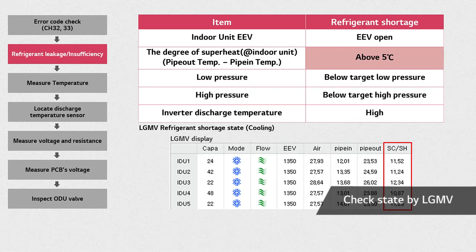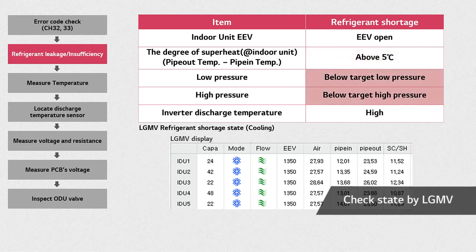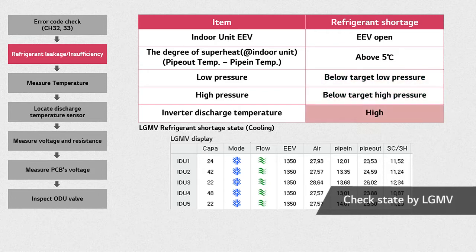Superheat is the difference between the pipe-out temperature and the pipe-in temperature of the indoor unit. Also, when both low and high pressure are below the target pressure for each, or the discharge temperature of the inverter is higher than usual, you can tell there is a lack of refrigerant.